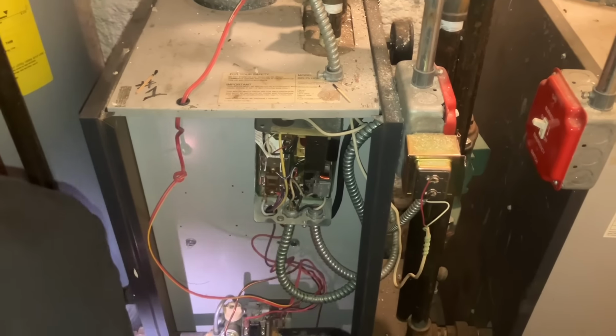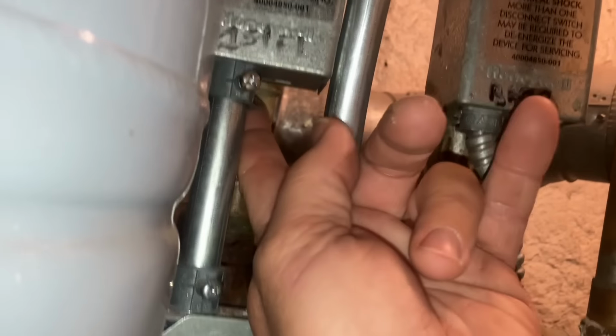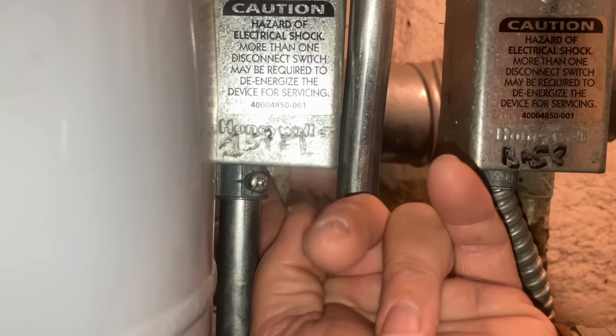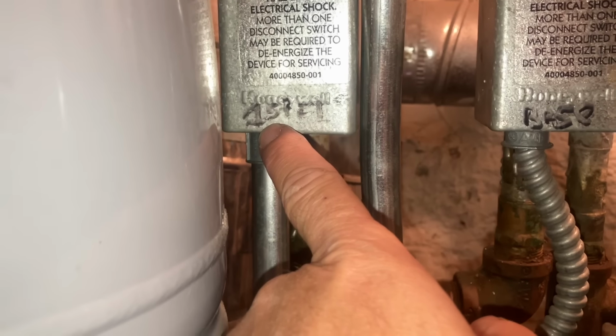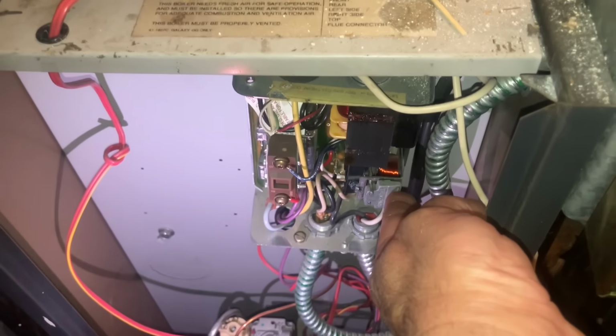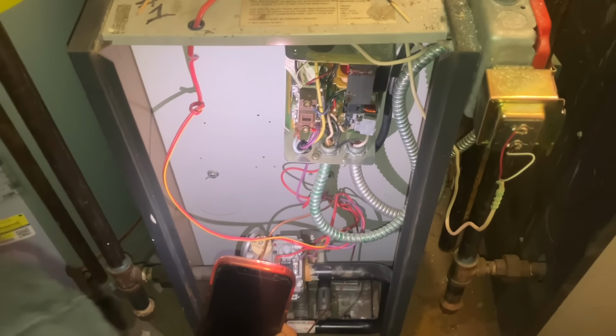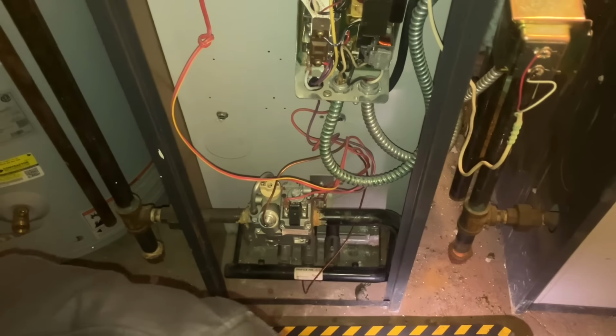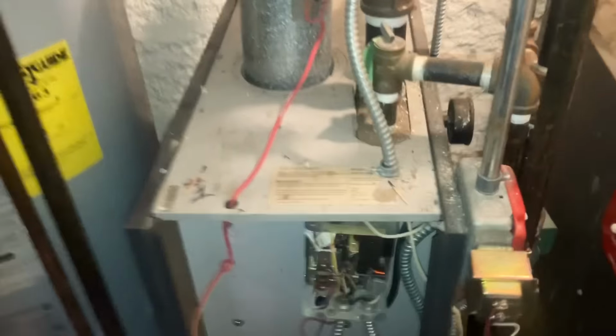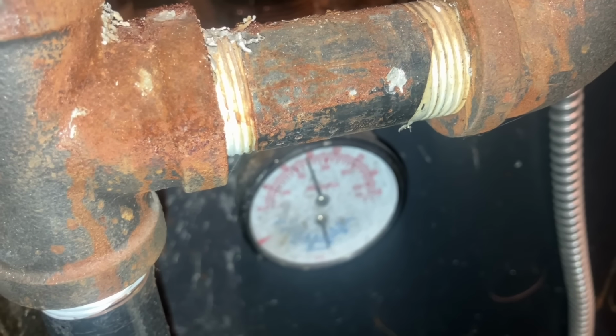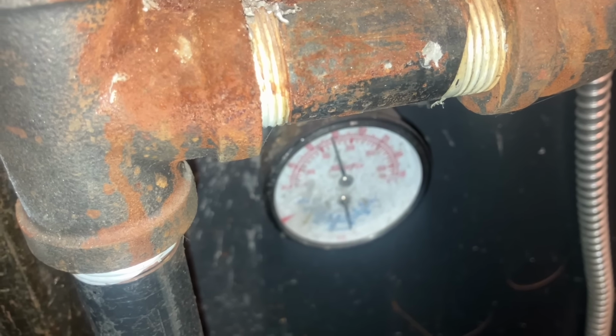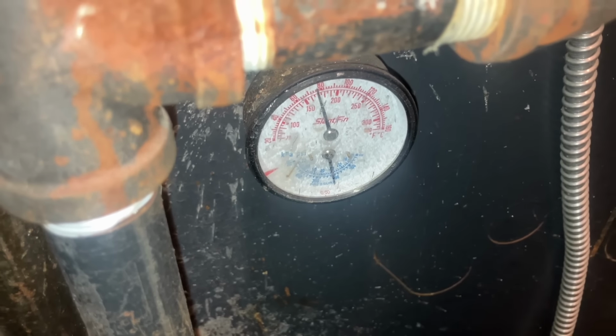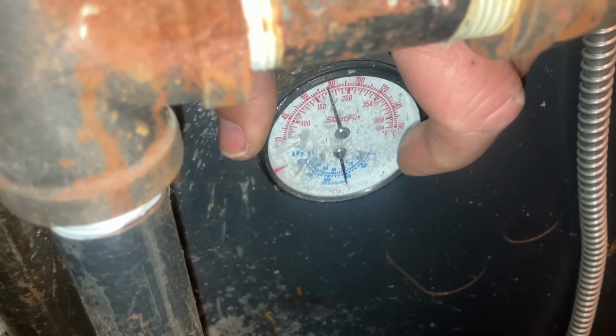Now that we know that the Aquastat is set for 180, power is on, and we have 2 zone valves. This one has no resistance. That's the basement zone, and that one, first floor, sorry, has resistance. So right now the basement is calling, and the thermostat relay is actively calling. So as long as our pilot is on and the gas valve is set to on, this should ignite. So let's see what our temperature is at. It's hard to see there, but it looks like it's at 180 degrees. Pressure's kind of high there as well. Looks like the pressure is at 30.